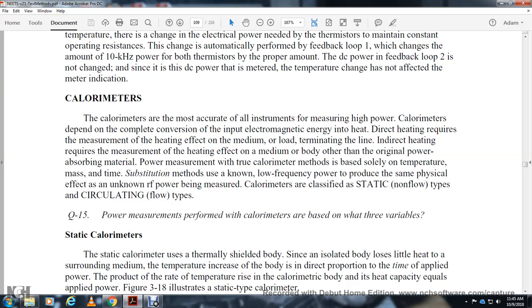Methods rely solely on the temperature of the mass and time, and substitution methods use known low frequency power to produce the same physical effect as the unknown radio frequency power being measured. Calorimeters are classified as static, non-flow type, or circulating flow type.